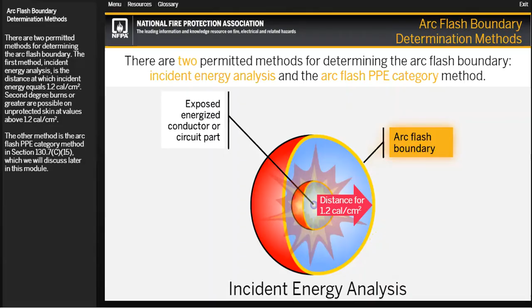For example, if you have this energized equipment, energized conductor, this is an arc flash boundary at which a second degree burn can occur. And the second degree burn occurs at an incident energy of 1.2 calories per centimeter squared. So this is the value which creates a second degree burn, and this is the standard for making an arc flash boundary.